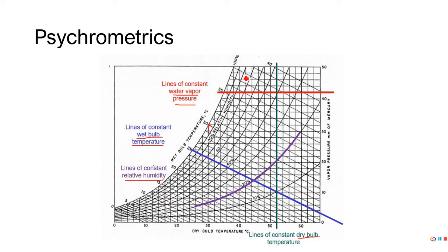Each of these lines that go up that curve, where it says relative humidity, represents the percentage of water the atmosphere is actually holding. What's 100% saturated at 25 degrees Celsius would only be about 20% humidity if we come out to 45 degrees Celsius.